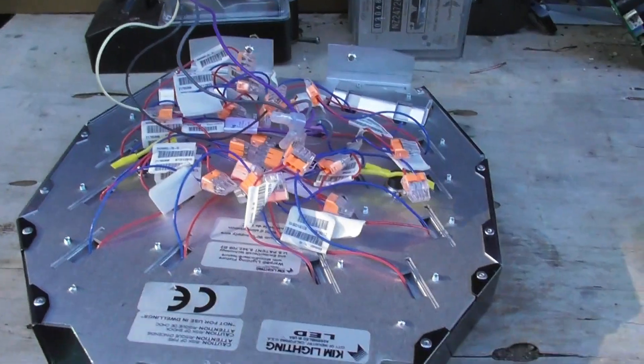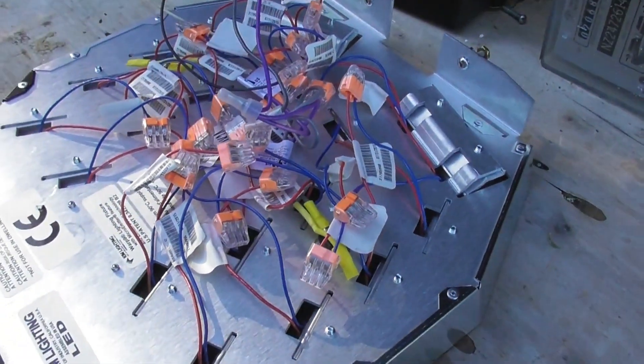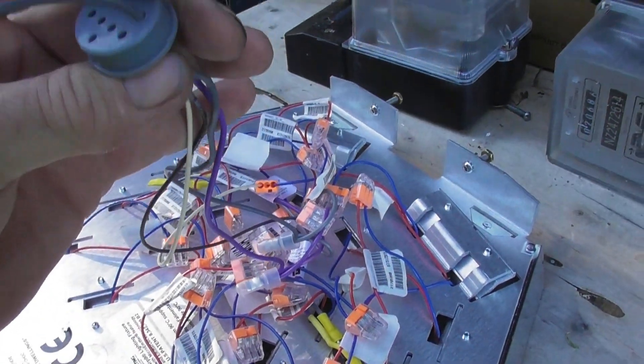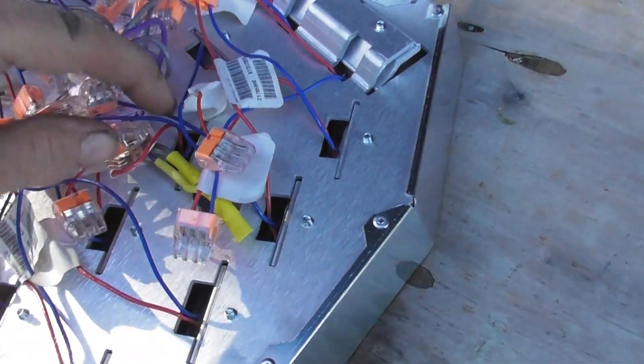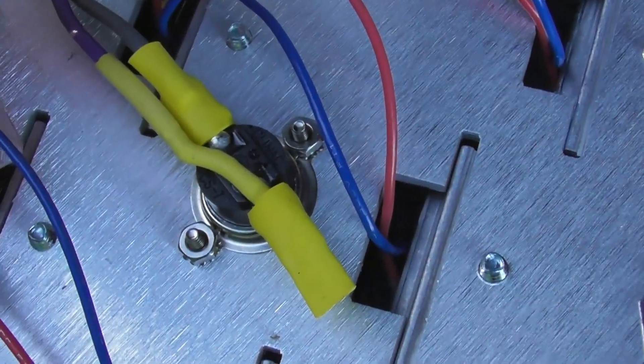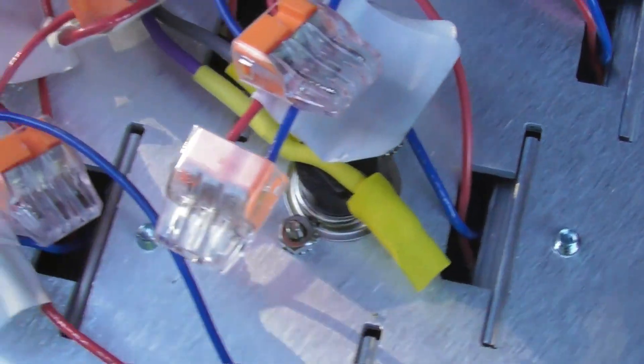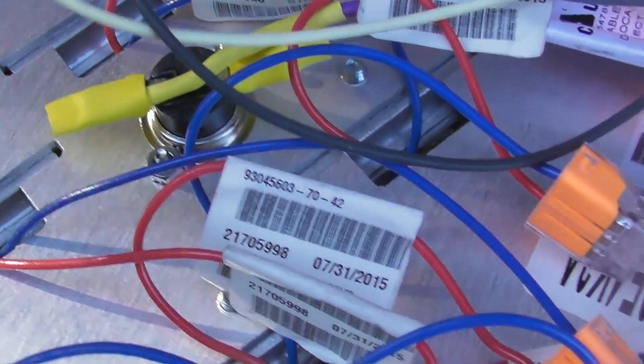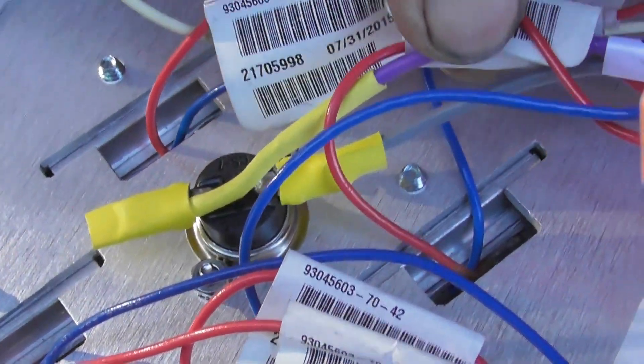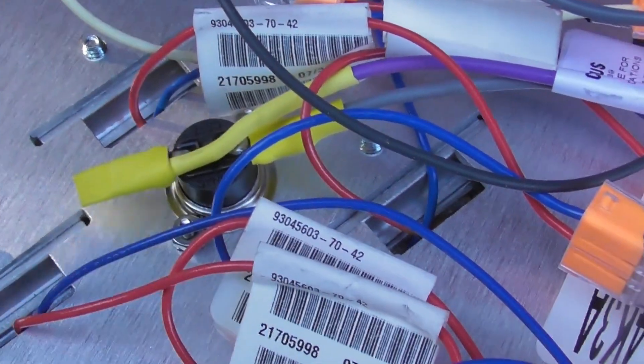I've done a bit of an analysis on the wiring. Incoming supply, I worked out the purple and the white. There's actually a couple of thermal sensors in here, heat sensors or thermal cutouts. There's another one here, so they are controlled by the purple and the grey wire. They're obviously a safety device going back to the power supply.